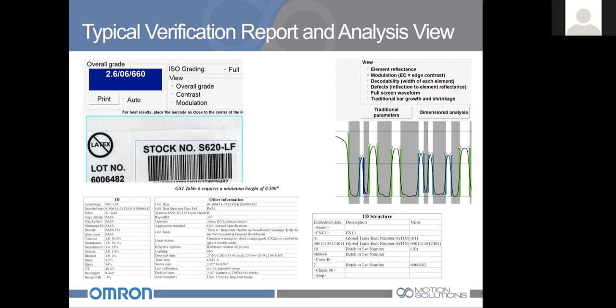Just a little bit more detail on the verification report. So on the upper left, when we use that handheld verifier, this is the information you'll get. So you may recall when we were looking at that GS1 standard, those 3 numbers separated by the backslash. So the overall grade of 2.6 in this case is better than the 1.5. So that gives you that assurance that you're complying with the GS1 minimum requirement, and gives you the view of the actual label.